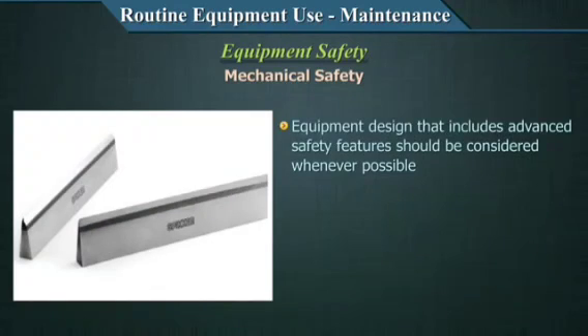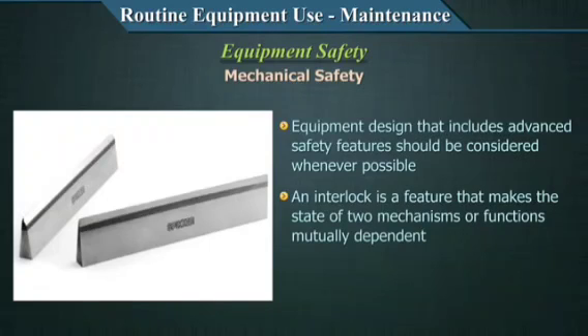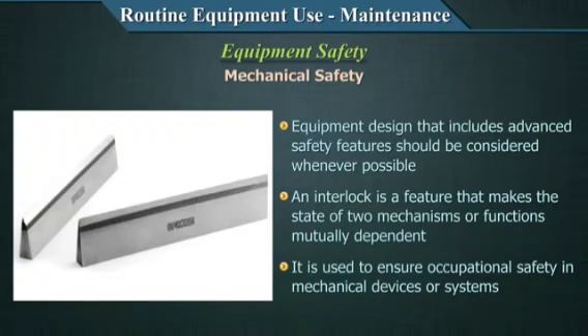Equipment design should include advanced safety features such as audible or visible signals - we already talked about this when discussing purchasing considerations. Availability of interlock or key lock systems and permanent shielding, etc., should be considered whenever possible. An interlock system is a feature that makes the state of two mechanisms or functions mutually dependent, used to ensure occupational safety in mechanical devices and systems. This is a very important concept because if a certain part is moving, that part will not move if the equipment is open - there will be a door connected to that moving part, so if the door is open, it will not actually move.